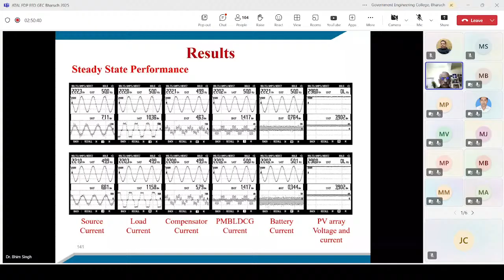Then we use a conventional synchronous generator with the solar. For this example, I asked one of my students to look into a hospital. Normally a hospital has a DG set, but we can install solar on the rooftop and a battery also, so we can reduce the diesel consumption. Even if the grid is not there, the cost of electricity from diesel is around 20 rupees per unit, but now we are getting solar at less than 2 rupees. So for the period we operate the generator, we can operate it at more than 80% load for a short period because we have a battery. We do not need to operate the generator at partial loading conditions. So we were able to work this out very successfully for a practical situation.